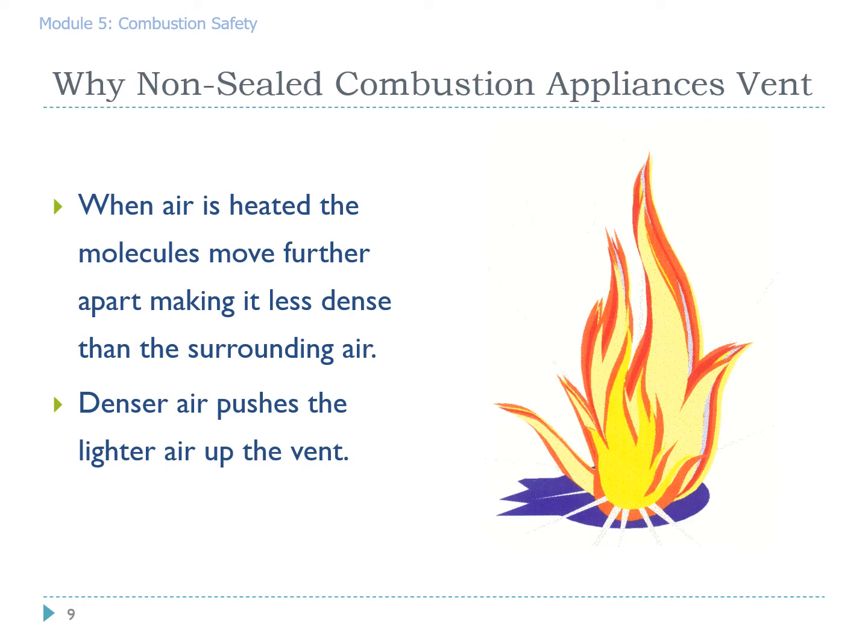Why do non-sealed combustion appliances vent? And by vent, we mean the smoke rises and goes out of the house, or the heated gases go out of the house. When air is heated, the molecules move further apart, and it becomes less dense than the surrounding air. What actually happens is the denser air around that lighter air then pushes those heated molecules up out the vent or up out the chimney.